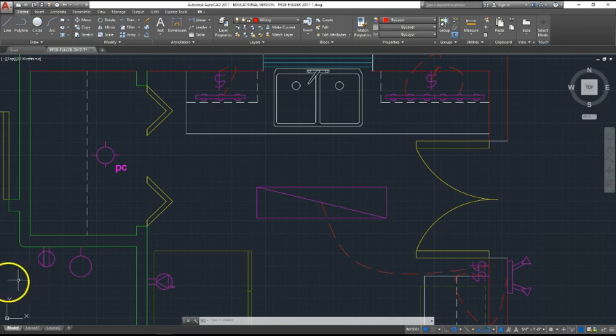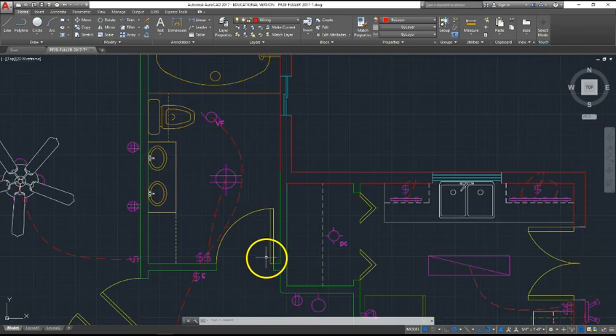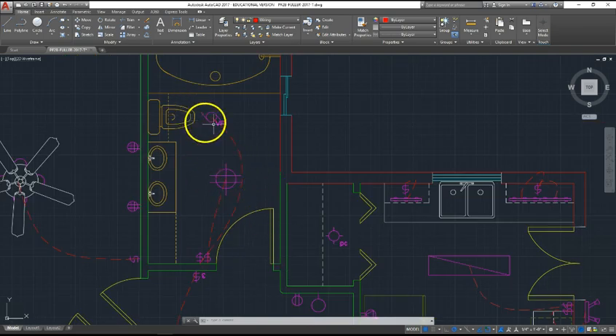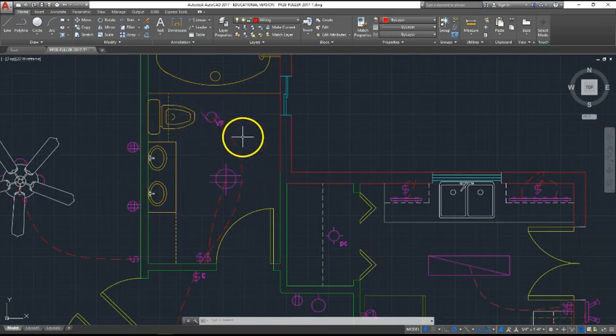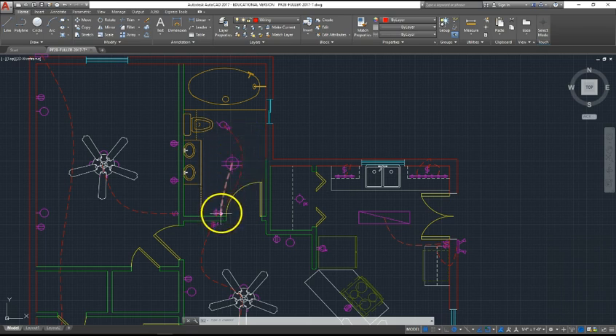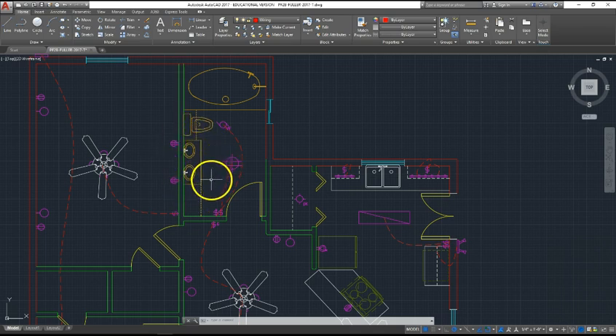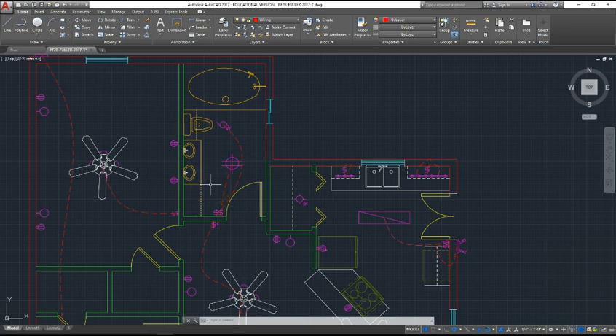In my bathroom, I have an exhaust fan represented by this tornado-looking symbol and a ceiling-mounted light fixture controlled by this switch on the wall. I have not placed my receptacle yet, but must do so within 36 inches of the sink. It, too, must be a GFCI because it is near water.